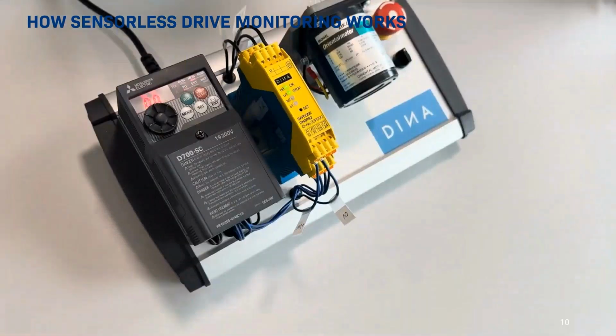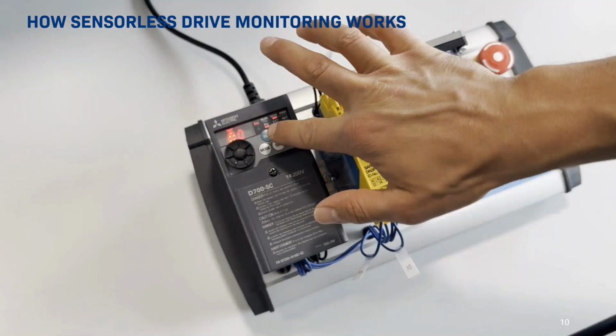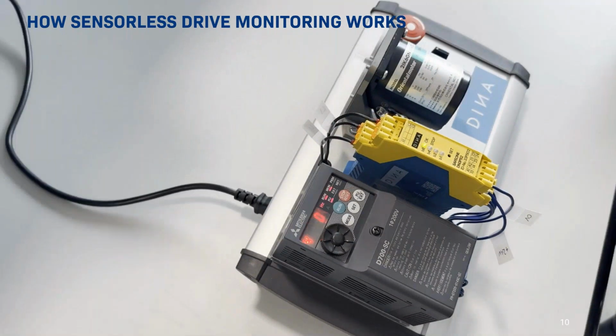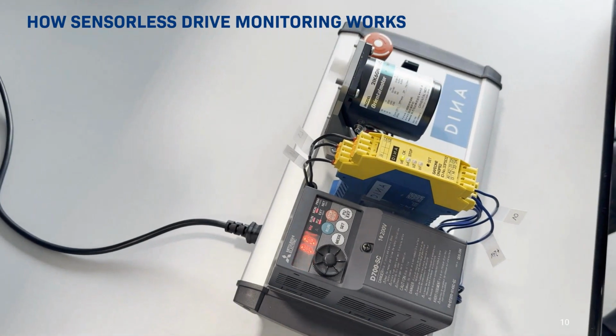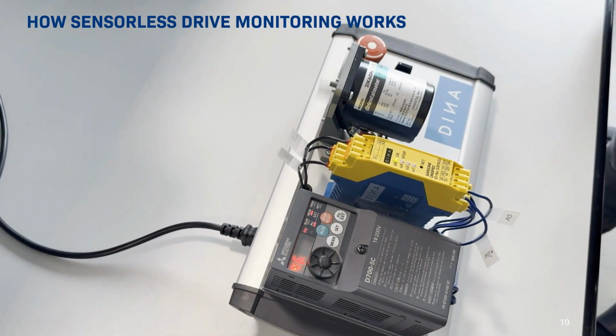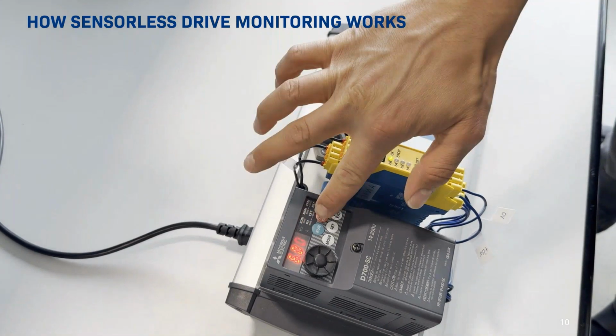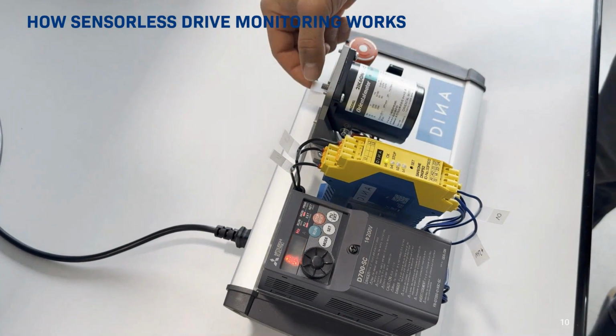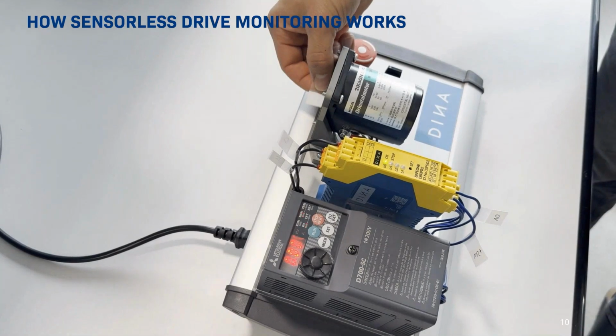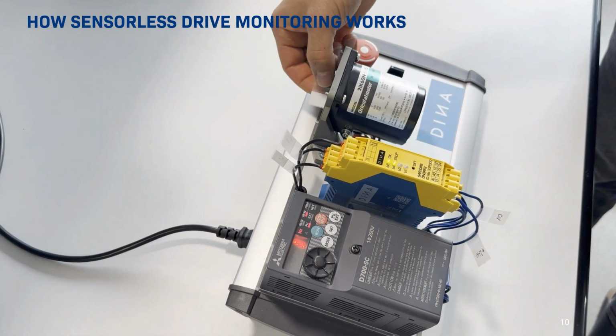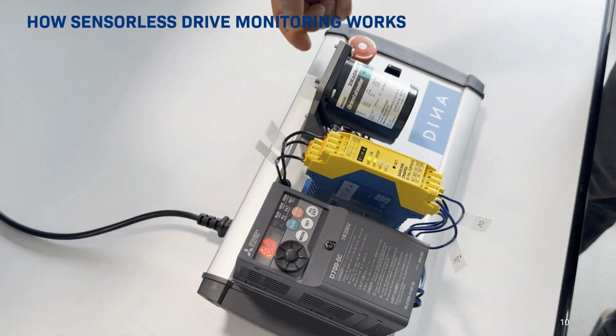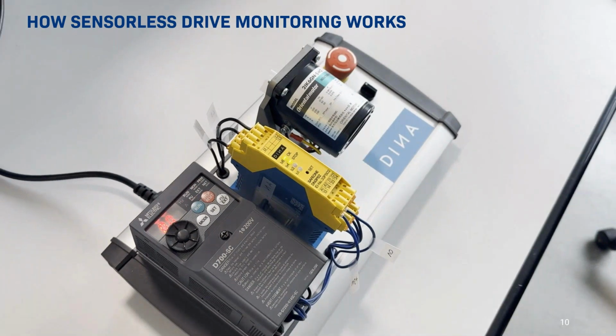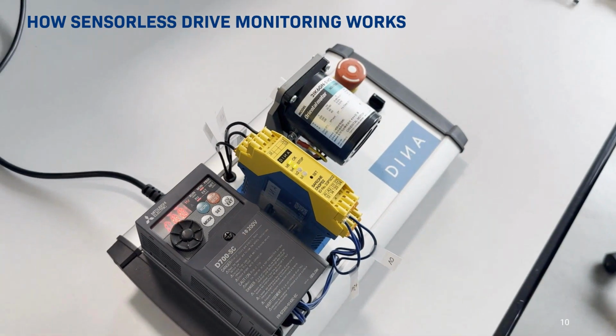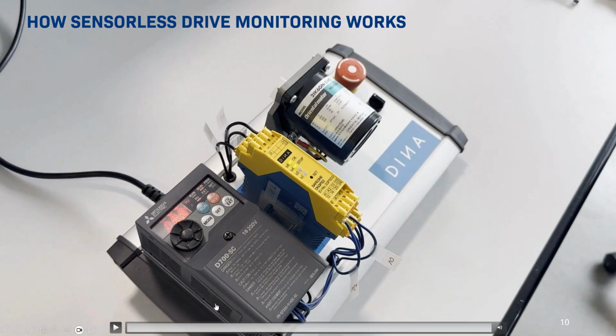If we start the motor's movement via frequency converter or manually, the sensorless standstill monitor module instantly recognizes the motion by calculating or evaluating the voltage signal. Upon recognizing movement, it immediately opens the safety relay contacts, ensuring the machine remains in a safe state until standstill is achieved. This demonstrates the simplicity of installing and connecting the sensorless modules.